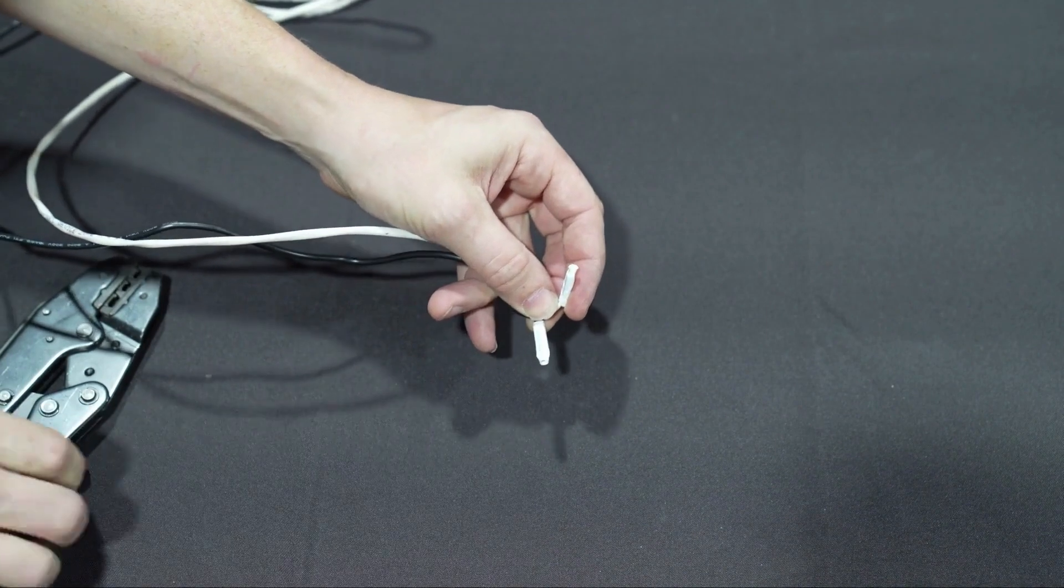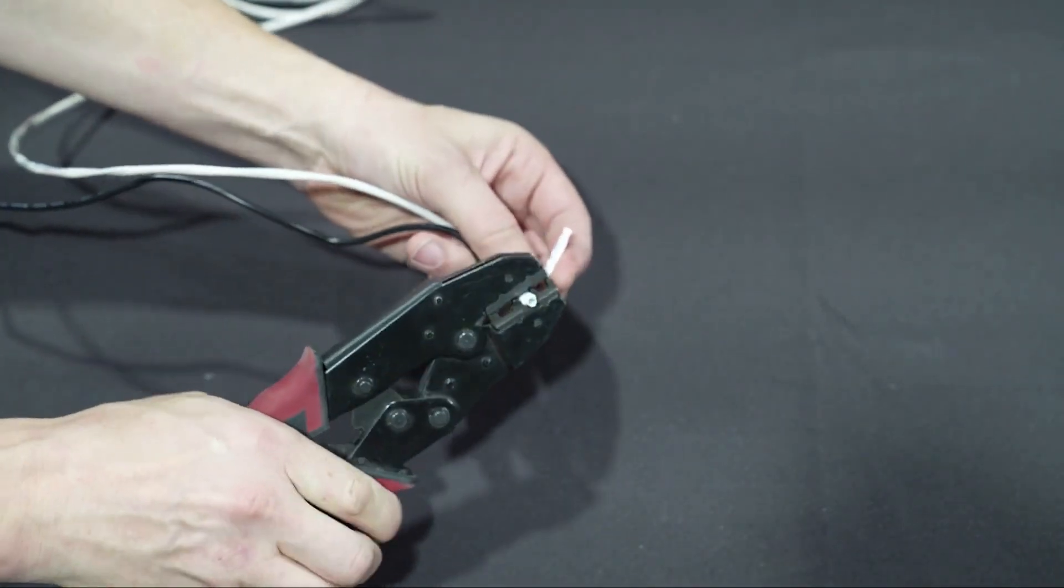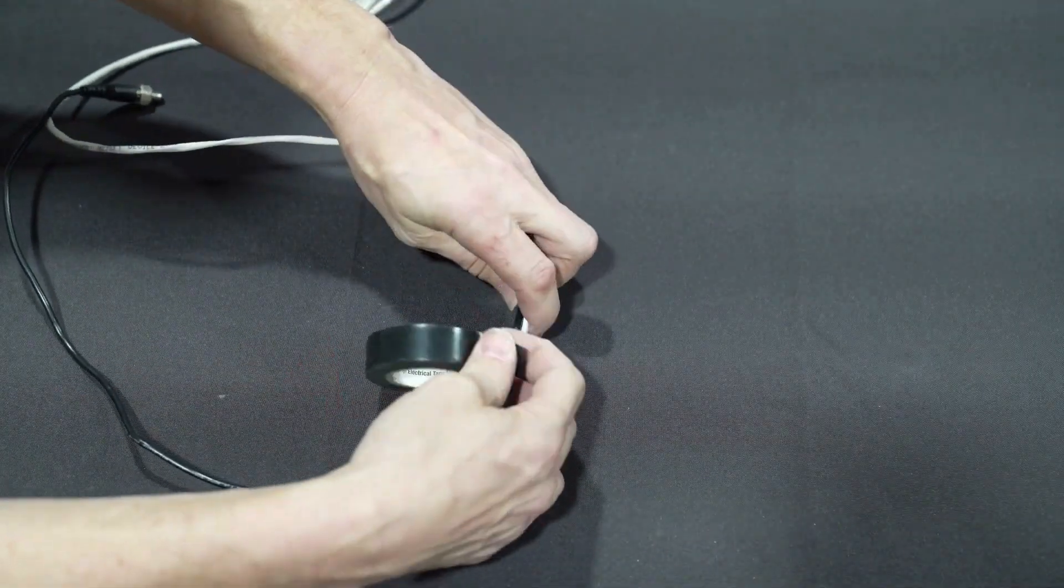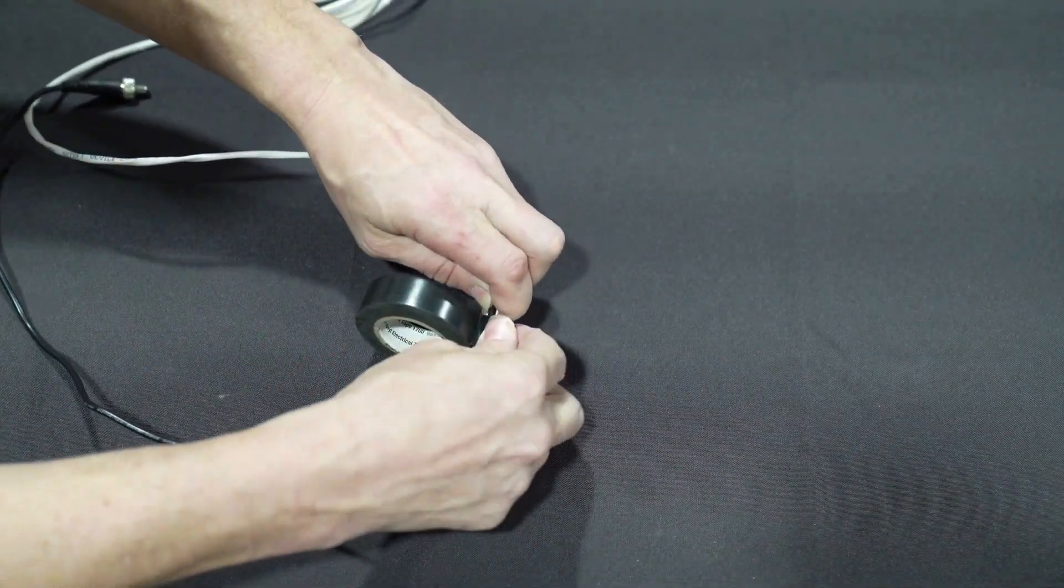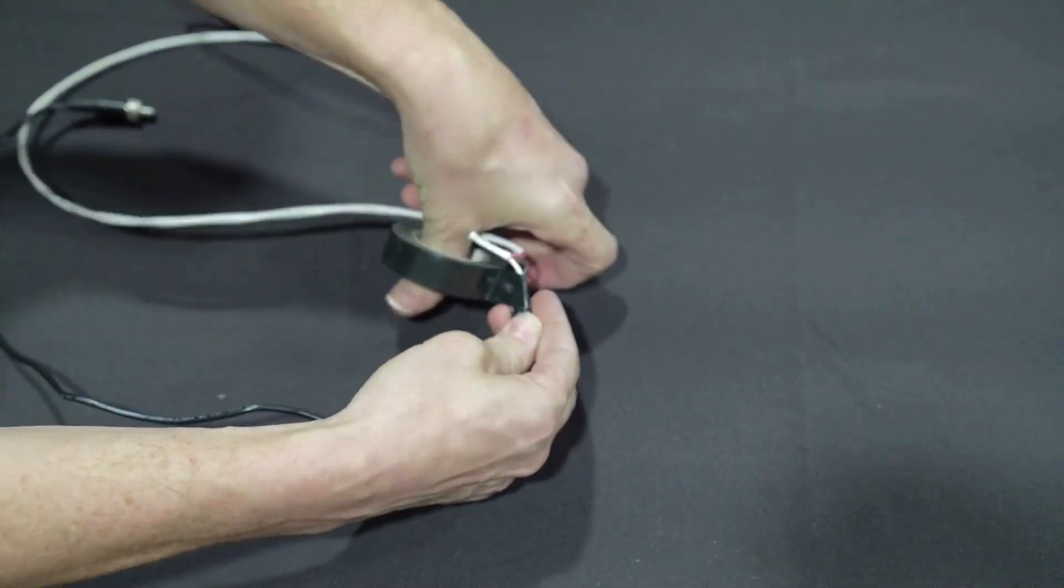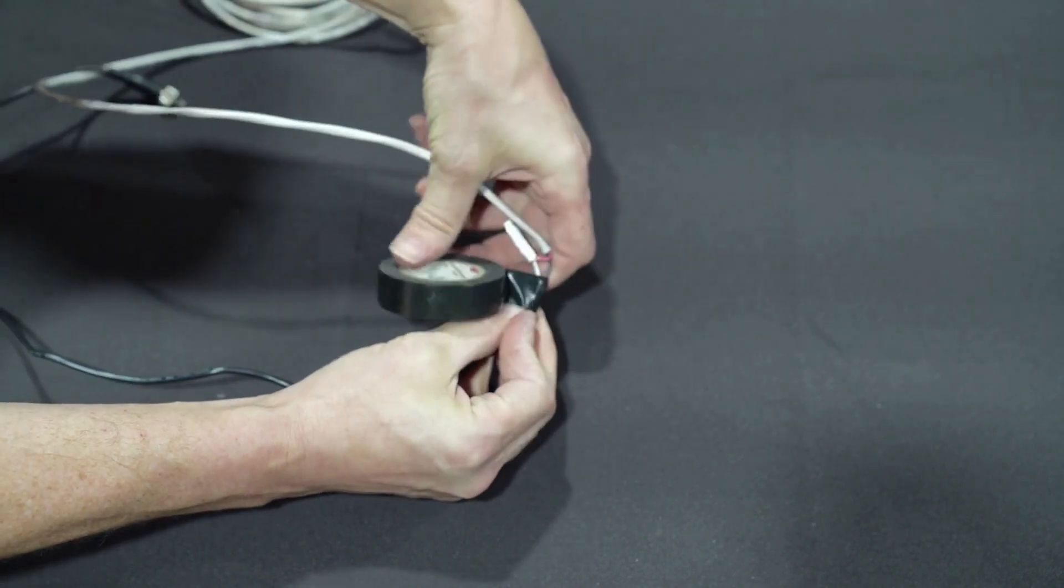In the base of the white inner conductor sheath, there should still be visible strands of the outer conductor. This is normal. Tape together the bundle to secure the splice from movement. Repeat the process on the opposite end of the power cable. Ensure that the same wires in the splice cable connect the inner and outer conductors.